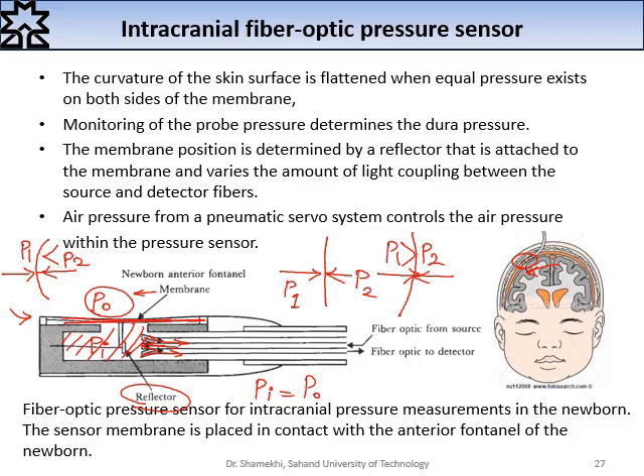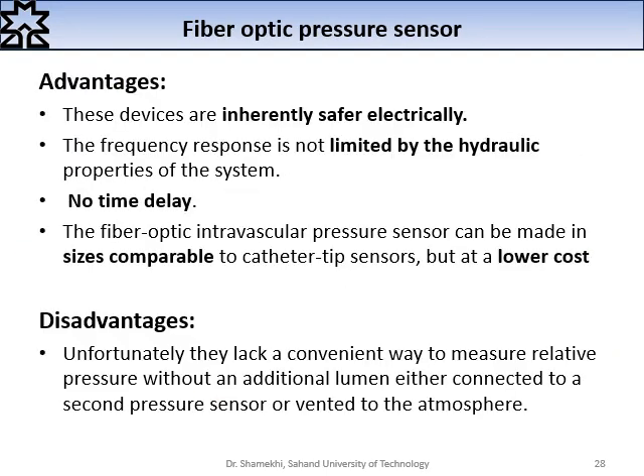You can read the text inside this slide by yourself. Fiber optic pressure sensors have some advantages. These devices are inherently safer electrically. We don't use any electric connection to the sensing side, to the detector side. The frequency response is not limited by the hydraulic properties of the system. And also there is no time delay because we don't have any hydraulic system. The fiber optic intravascular pressure sensor can be made in sizes comparable to catheter tip sensors, but at a lower cost, because all materials consist of some plastic or glass, and the price of these materials is low.